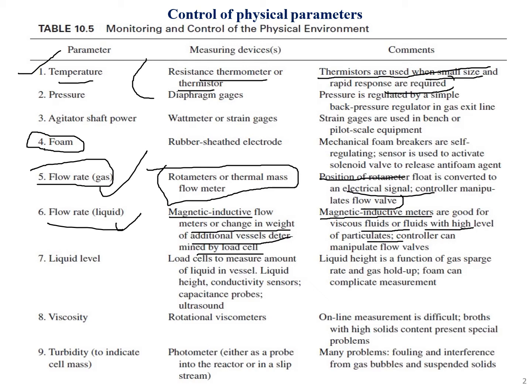The seventh point is liquid level. Load cells measure the amount of liquid, and it can also be measured with the help of probes — there are conductance probes, capacitance probes, or ultrasound probes. Liquid height is a function of gas sparge rate and gas hold-up. Foam can also complicate measurement by giving a false reading.